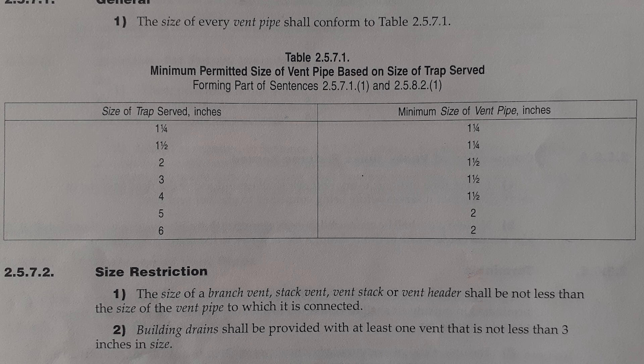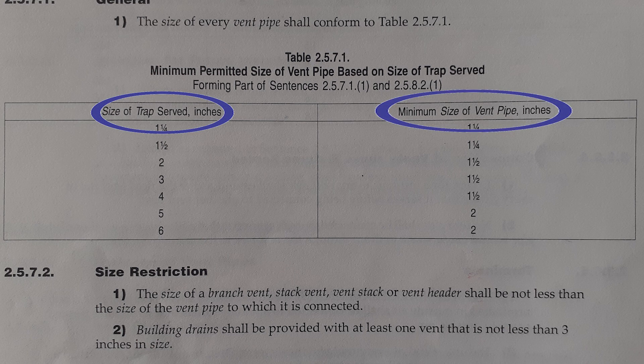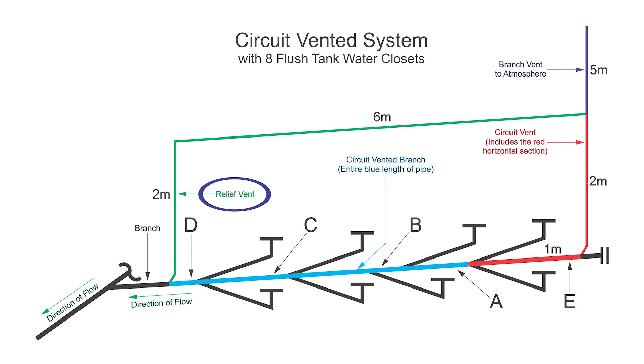Table 2-5-7-1 is a very important table used for all vents. It looks at the size of trap being served and gives a minimum vent size. In this example we have 3-inch water closet traps, so we need a minimum of 1-and-a-half-inch vent. Therefore the relief vent needs to be a minimum of 1-and-a-half inches.